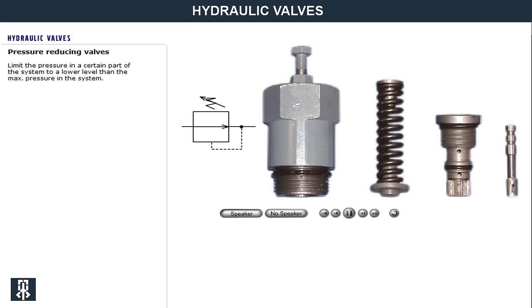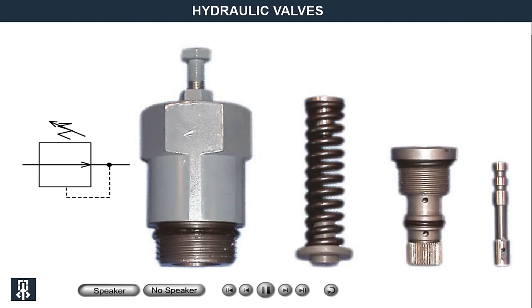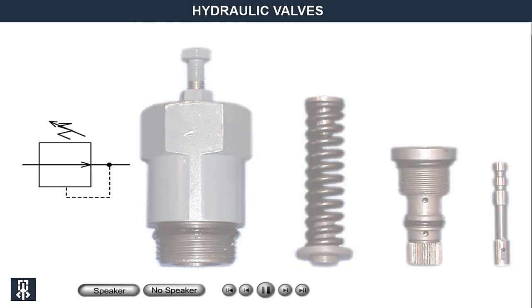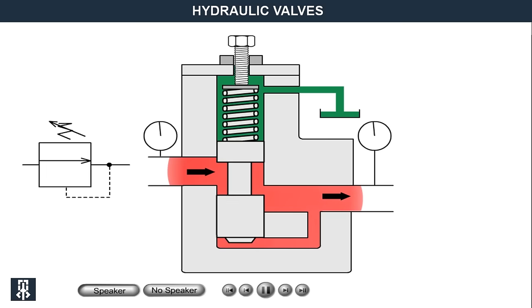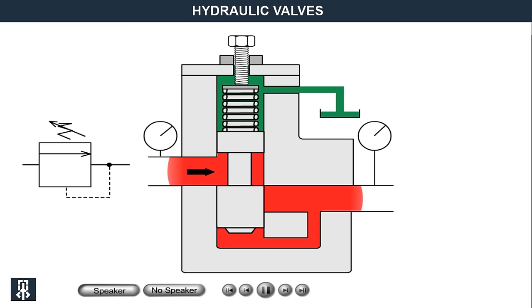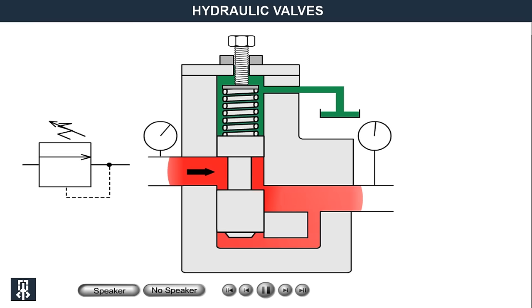Pressure reducing valves limit the pressure in a certain part of the system to a lower level than the maximum pressure in the system. As a rule they also maintain maximum pressure in the subsystem at a constant value regardless of pressure changes in the main circuit. When the fluid pressure in the branching line has reached the set value, the oil pressure in the channel lifts the valve slide and the slide closes between inlet and outlet. The spring housing is connected to tank to prevent hydraulic lock.